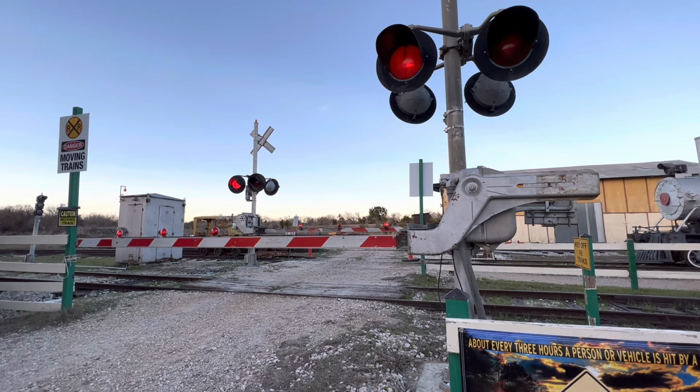As for this problem here, someone lifted up the gate, it'll crash back down when the signals reactivate. I'm going to show that in just a minute. And the other problem is that you could actually fix the problem temporarily, and then a couple activations later, the problem will happen again and could cause another dangerous situation. I never suggest anyone to lift up crossing gates if you're not supposed to. It's a serious issue, I see it all the time.